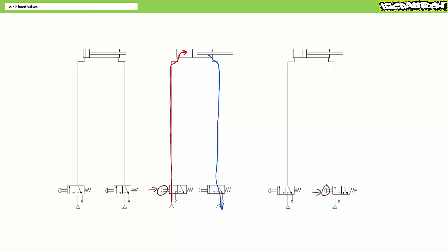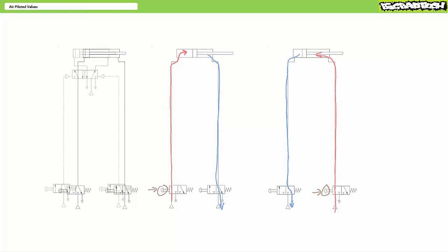When an operator releases push button one and presses push button two on the right, the cylinder does retract, but it retracts slowly and weakly due to the pressure losses in the long line feeding the rod end. To compound this poor performance, the line exhausting the cap end encounters a lot of resistance such that the cylinder retracts doubly slow and doubly weak.